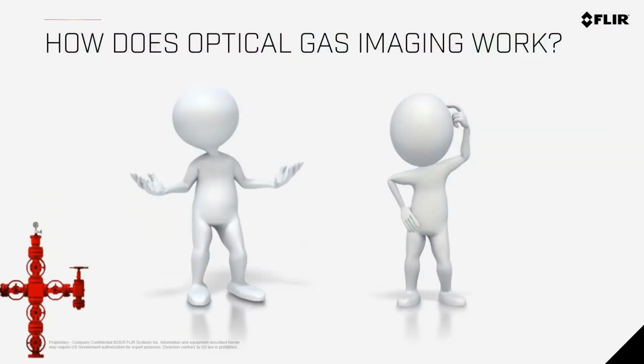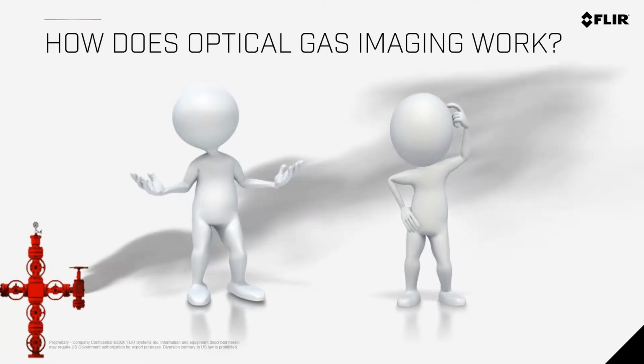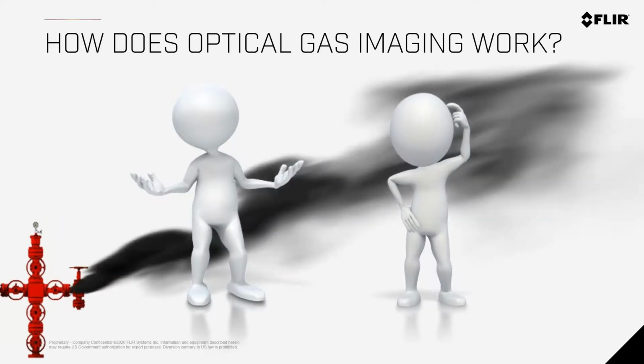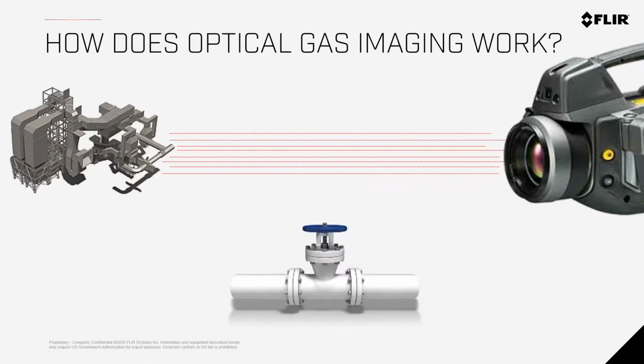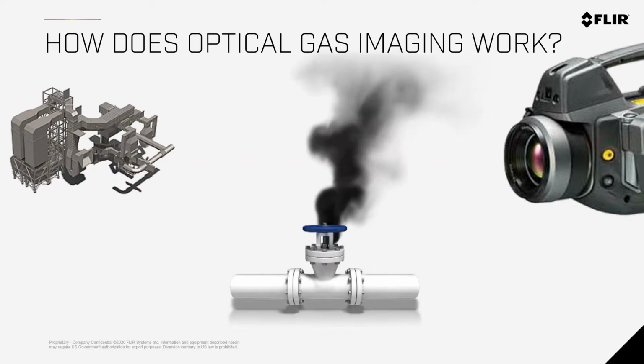So we'll dig in just briefly into how optical gas imaging works, right? A little bit behind the camera, how this camera actually detects the gases that are leaking. The camera sees more than gas only. It sees the things in the background, like pipes, people, the ground, plants, et cetera. But when there is a gas leak, that gas blocks the lens from seeing those things, and so those objects do not reach the camera.